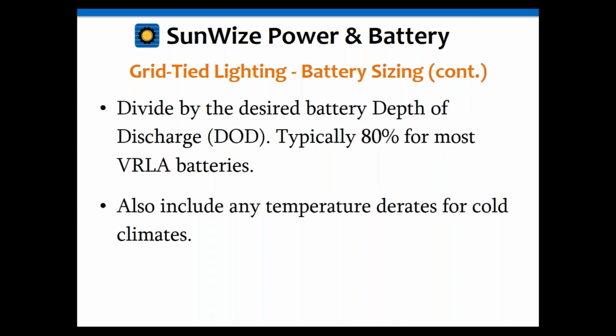Now, what that does not include is any other derates you might want. Temperature is an important one. If you're in a colder climate, you may want to add a temperature derate to that. In most cold climates, it's not unusual to use an additional 20% derate for that. So you may want to divide those batteries, whatever that capacity is, by an additional 80% again for some temperature derates. But I would refer you to the battery manufacturer's temperature derate curves for that. So you would need to know the temperature in your area, and then look at those derate curves, and then apply whatever derate factor you wanted to for those.